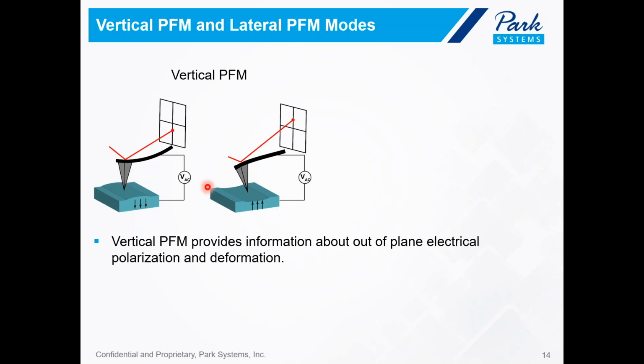The position sensitivity of the photodiode allows PFM to identify the direction of the electrical polarization in active piezoelectric and ferroelectric domains. So in this image shown on this slide, if there's no deflection of the cantilever, the laser spot would stay right here at the center of our photodiode, or the 0, 0 coordinate. So the first mode shown here is vertical PFM, where one can imagine that the laser will deflect vertically as the cantilever deflects up or down in response to the material which is changing as a result of its piezoelectric properties. So vertical PFM provides information about out-of-plane electrical polarization and deformation. Out of plane meaning perpendicular to your sample surface.